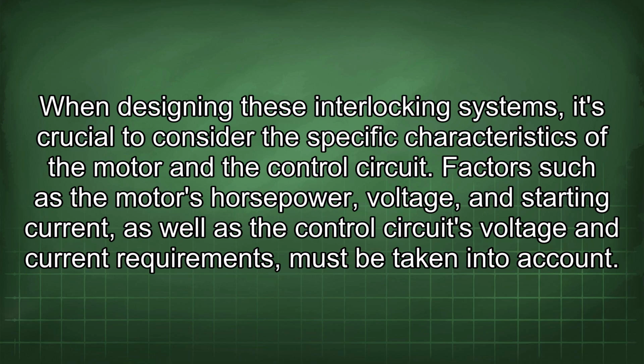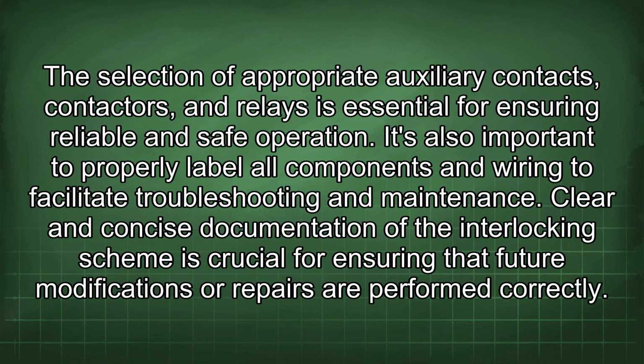When designing these interlocking systems, it's crucial to consider the specific characteristics of the motor and the control circuit. Factors such as the motor's horsepower, voltage, and starting current, as well as the control circuit's voltage and current requirements, must be taken into account. The selection of appropriate auxiliary contacts, contactors, and relays is essential for ensuring reliable and safe operation. It's also important to properly label all components and wiring to facilitate troubleshooting and maintenance. Clear and concise documentation of the interlocking scheme is crucial for ensuring that future modifications or repairs are performed correctly.